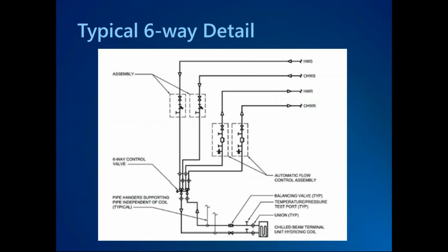Next up, we're looking at what we would call a traditional detail. And you'll see a lot of similarities between a 6-way piping detail and a 2-way or 3-way piping detail that you may see for a VAV or a fan coil. First thing on the supply side, we want some sort of strainer, isolation, and a PT tap. That's going to feed into the 6-way control valve. The 6-way control valve is going to feed to either a single chilled beam or a zone, and we'll talk about the piping that happens down in the dual temperature zone a little bit later.